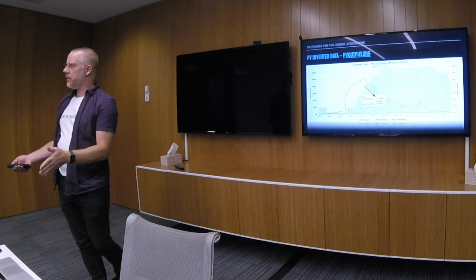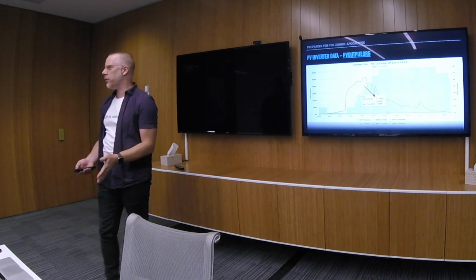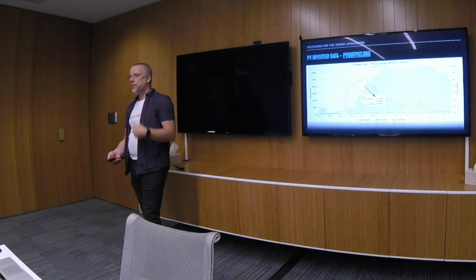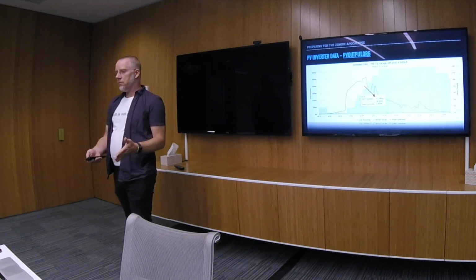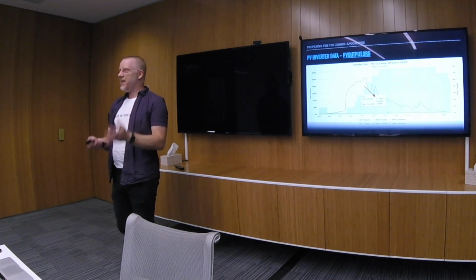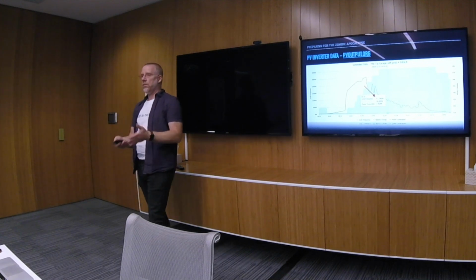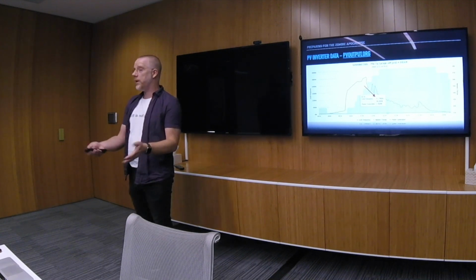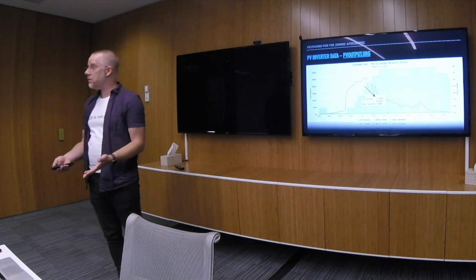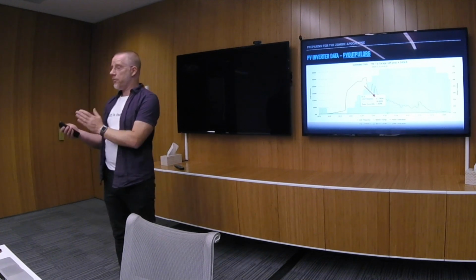I don't discharge it less than 50%, so I've really only got 38 kilowatt hours of charge available to me. If I use, say, 10 kilowatt hours a day, that gives us effectively 3 days of autonomy. If there's no sunlight for 3 days, the battery can go from 100 to 50%.